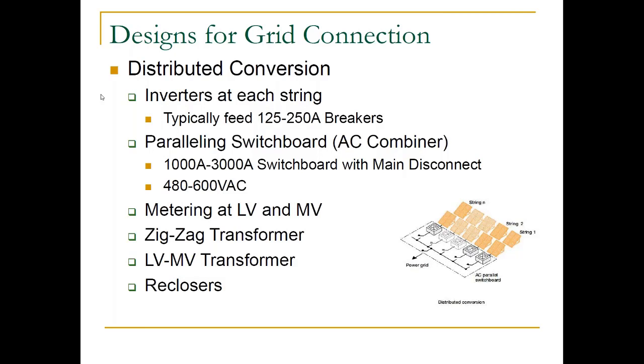In this connection out to the grid, that's where we start to find differences in an installation or developer requirements, utility requirements on what kind of transformer connection it is. Obviously, it's going to be a low voltage to medium voltage step-up transformer to connect to the grid. Is it going to be a standard pad mount transformer with just an air terminal chamber, some load break elbows maybe, or is there going to be any kind of disconnect or fuses in that transformer? Those are certainly options that are available. More so nowadays in certain markets, we're seeing reclosers. It could be a pad mount, or it could be a pole mount recloser.